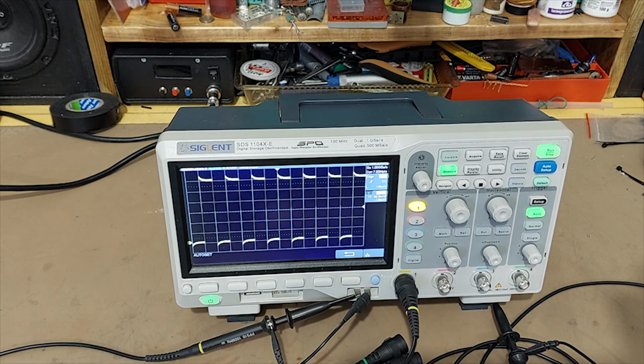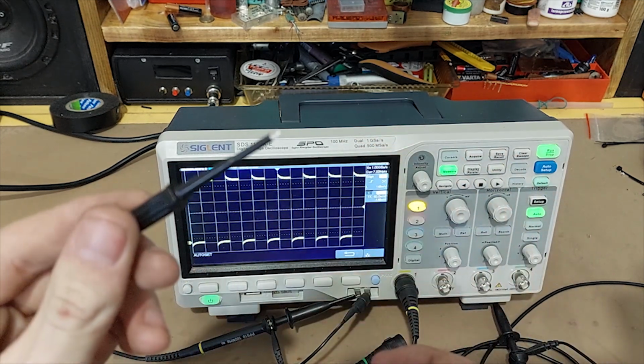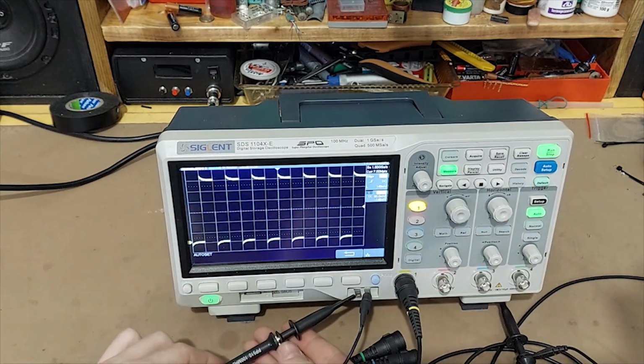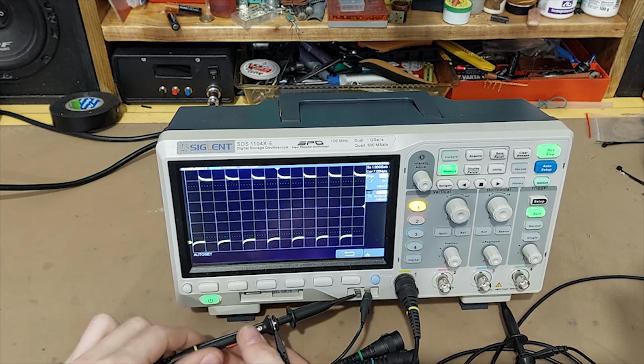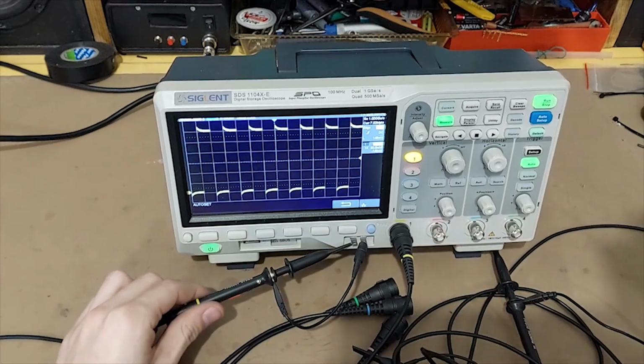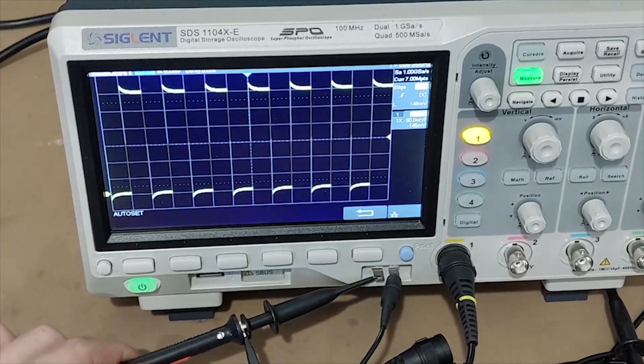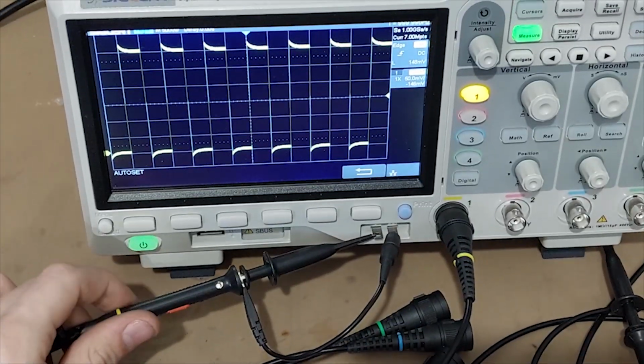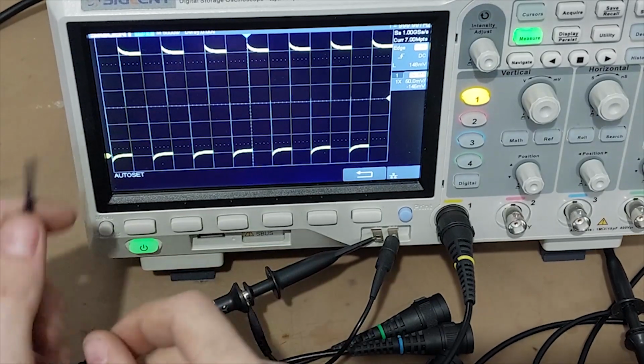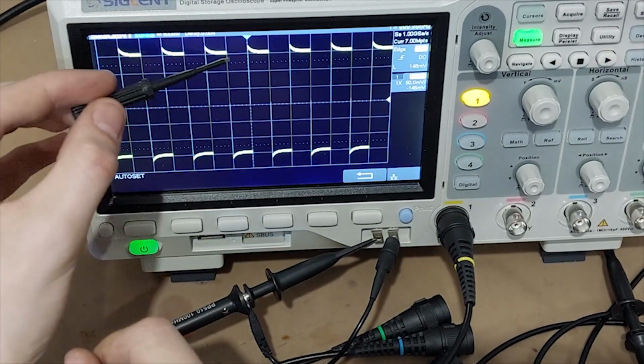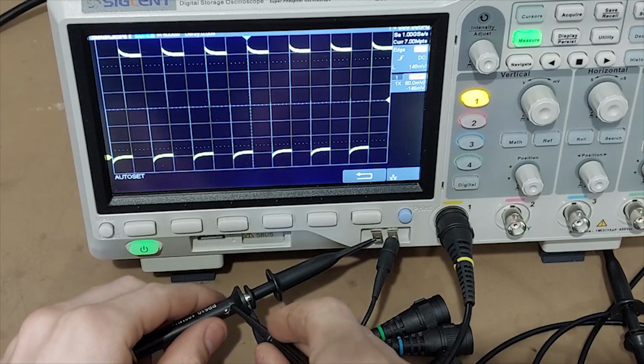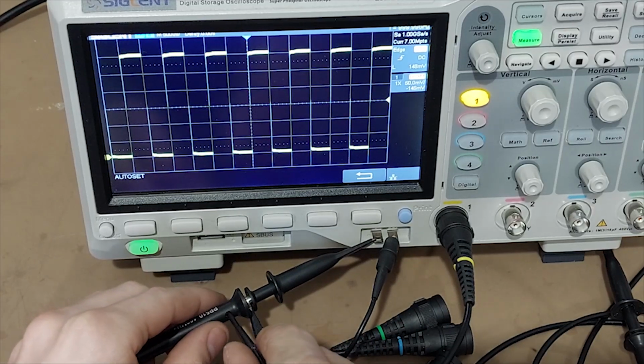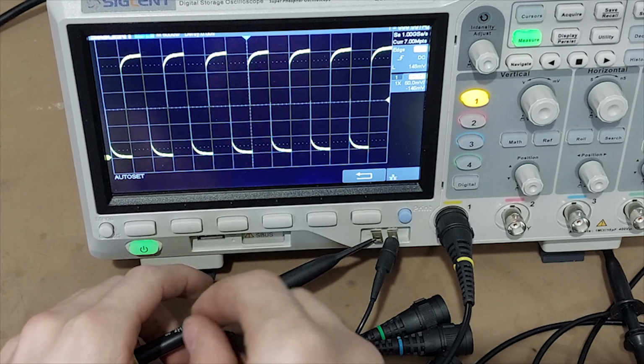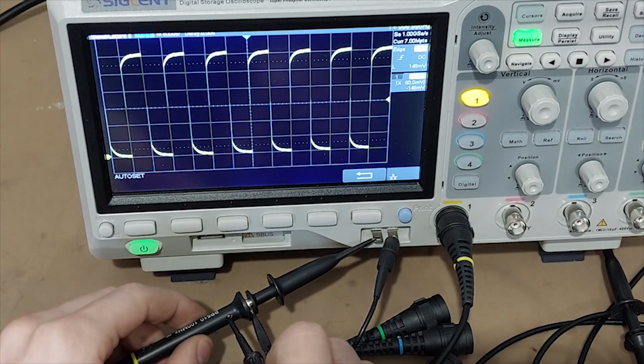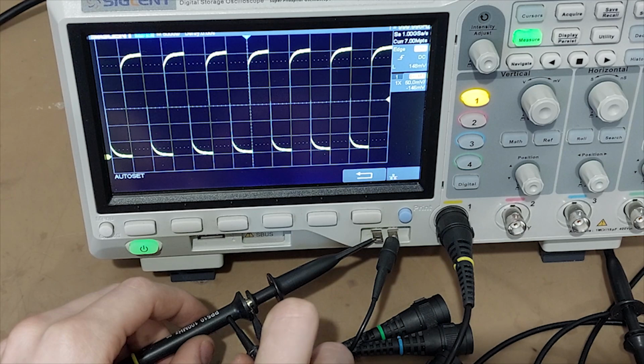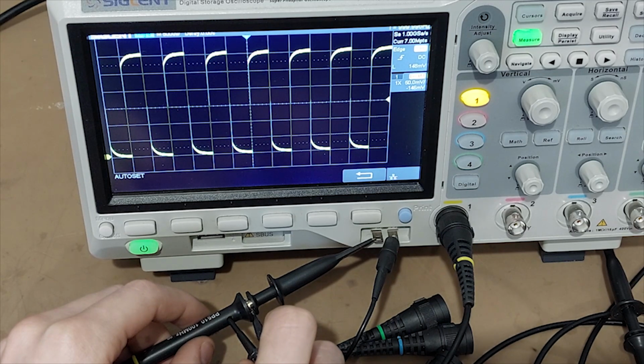And to calibrate it you take this included tool and you find the calibration screw right on the scope here, right here. And then you need to adjust it so that it looks like a square wave and there are no spikes on top or going inwards. It needs to be a perfect square wave. So you just put your tool in and hold your tongue at the right angle and you calibrate it.